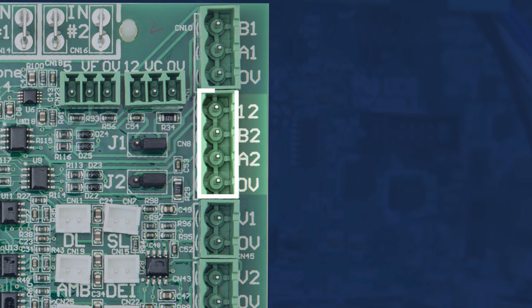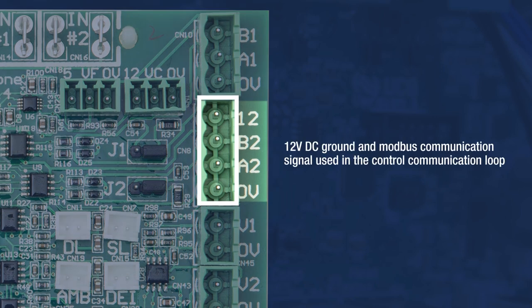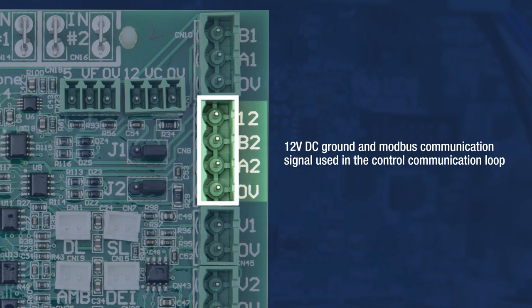12V, B2, A2, and 0V provide a 12V DC ground and Modbus communication signal that is used in the control communication loop. This loop may include slave UC8s, an indoor unit controller, inverter drive, or TempoZone factory supplied thermostat.